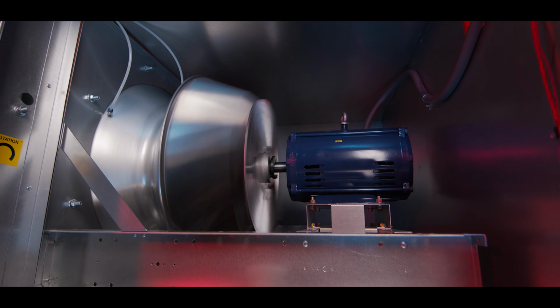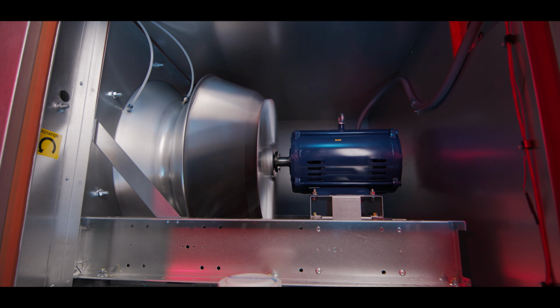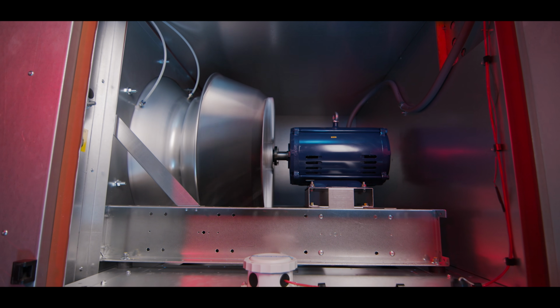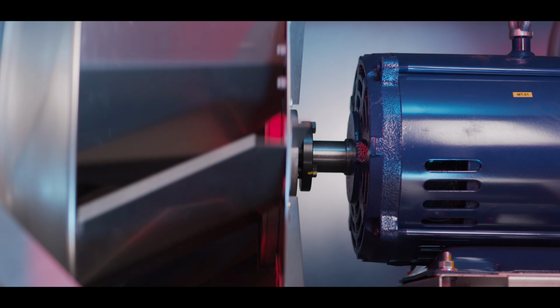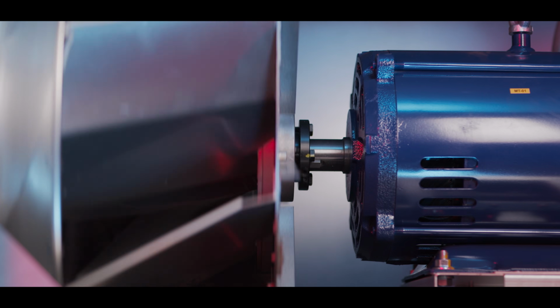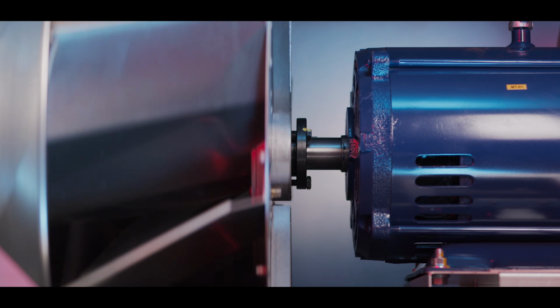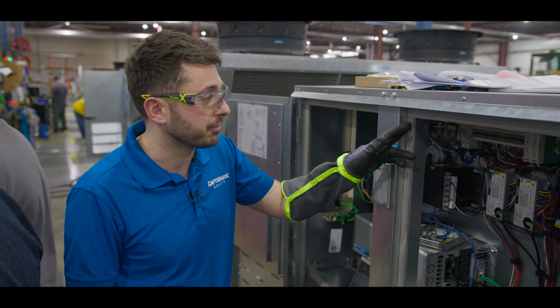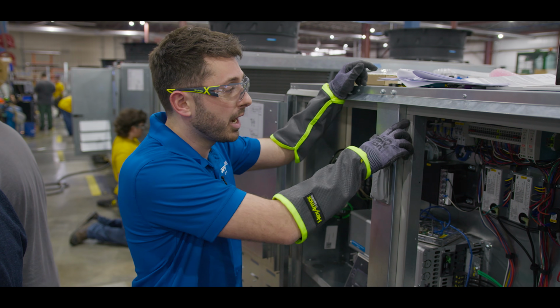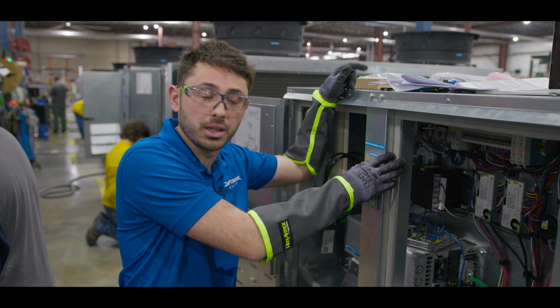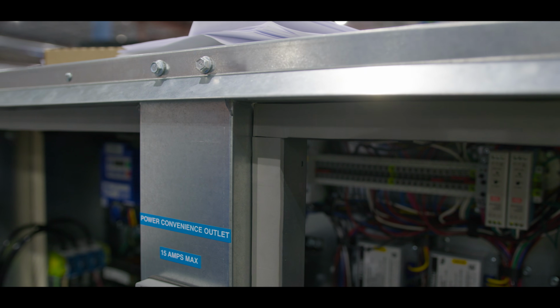These wheels create an enormous amount of vacuum inside the unit to maintain the required airflows, meaning if there are any leaks, untreated outdoor air would easily make its way into the building. So something that's really simple but can be taken for granted and cause major issues is how well these gaskets seal and the cuts on the gaskets themselves.